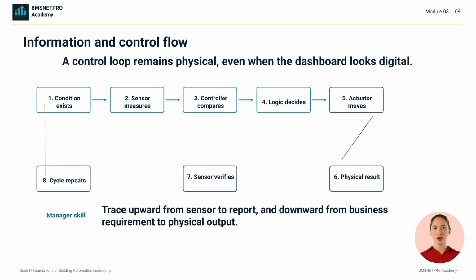A control loop starts with a physical condition. A sensor measures it. The signal reaches a controller. Logic compares the measurement with the intended state. The controller issues a command. An actuator changes the physical process. The sensor measures the result, and the cycle repeats. Supervisory and enterprise systems add context, history, alarms, analysis, and human decisions, but the fundamental loop is still physical. A BAS manager should be able to trace a point upward and downward.